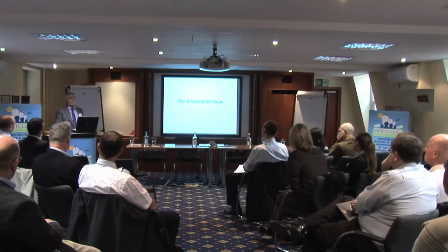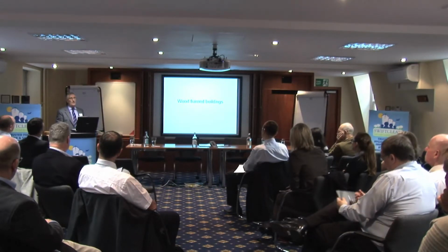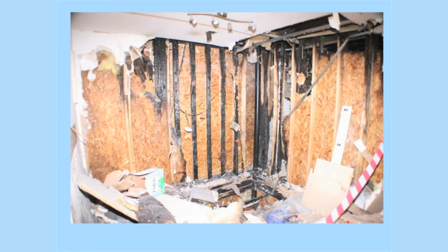But this is a fire that should have been no more than a few £1,000s, that started in a little cupboard where the consumer's installation equipment was located. The route by means of which the cables passed into the cavity of the preformed modular timber construction had not been stopped, and so the fire got into this cavity. And of course, the cavities are bounded on both sides by oriented strand boards, which have a load-bearing requirement, and this is depended upon in these structures. And here we have an example of the way in which the fire, once it's been opened up, has been progressing like a rat in a drain pipe throughout the building.